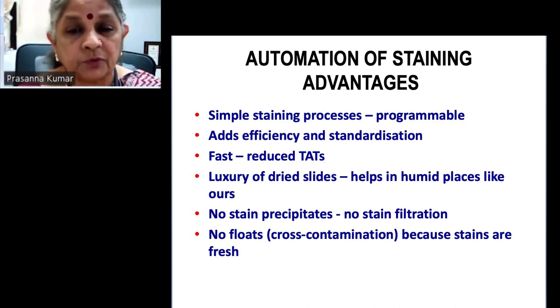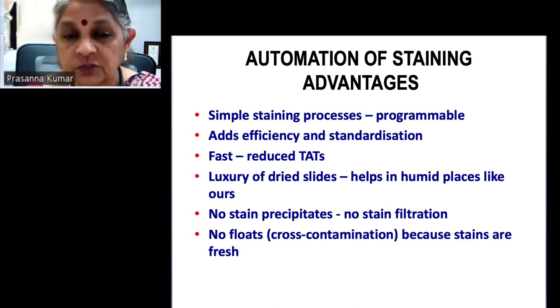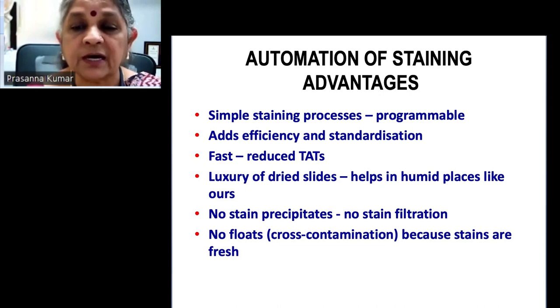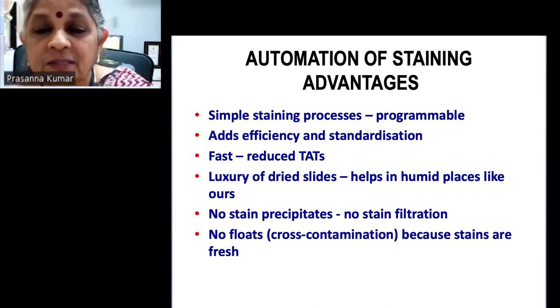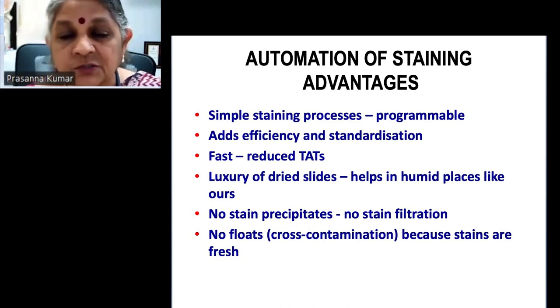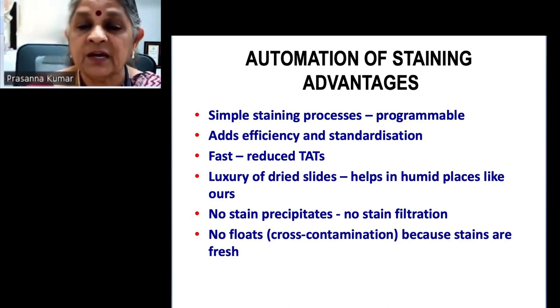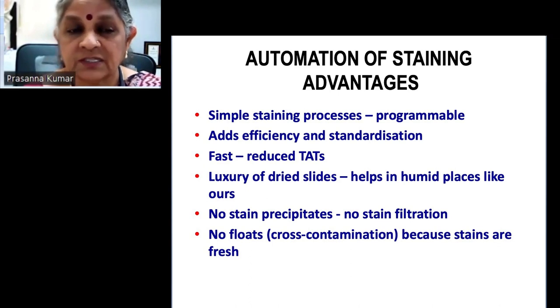The staining procedure is programmable, adding efficiency and a more standardized protocol. Automation means reduced turnaround time. You get slides that are dry straight out — just like a washing machine — which really helps in humid places where we had to wait 15 minutes to half an hour for slides to dry. There are no stain precipitates, no need to filter stain, no floats, and no cross-contamination because the stains going through the nozzle jets are very fresh.